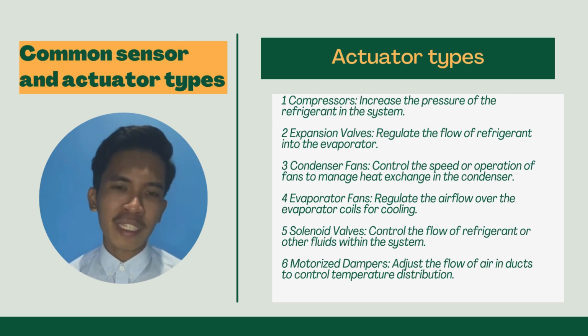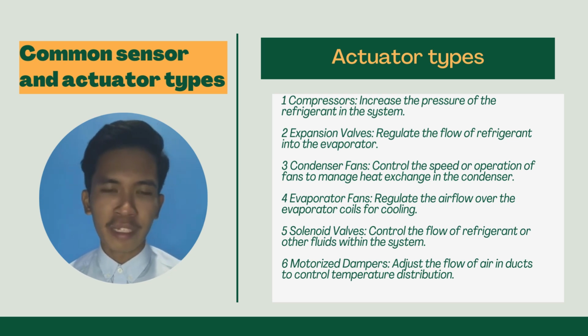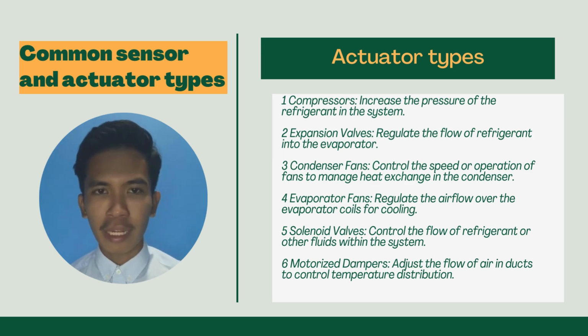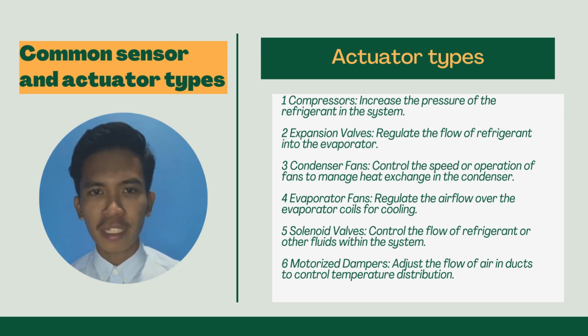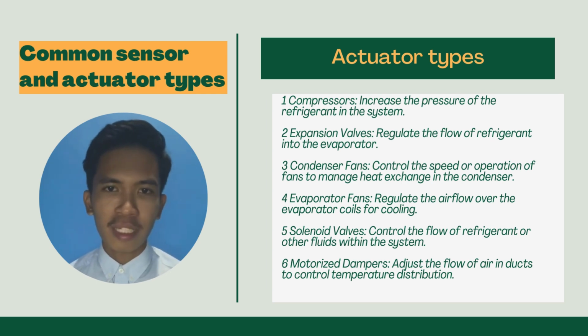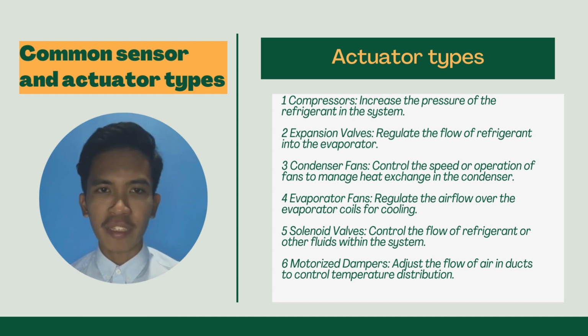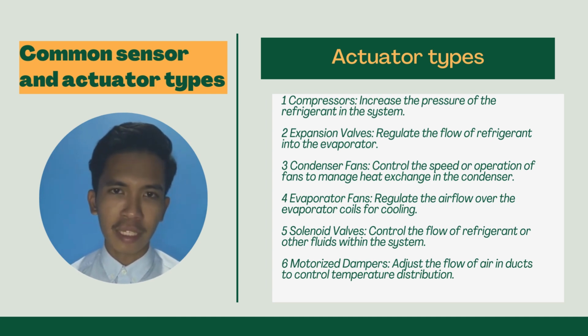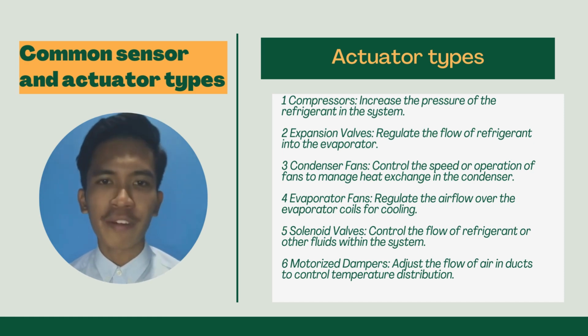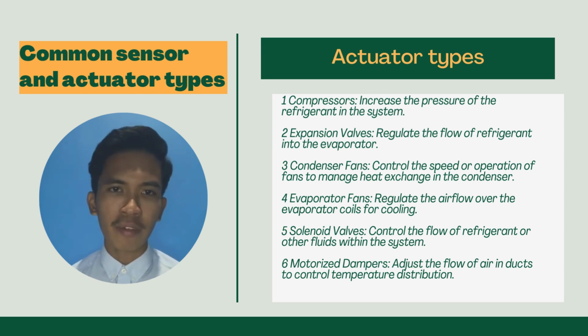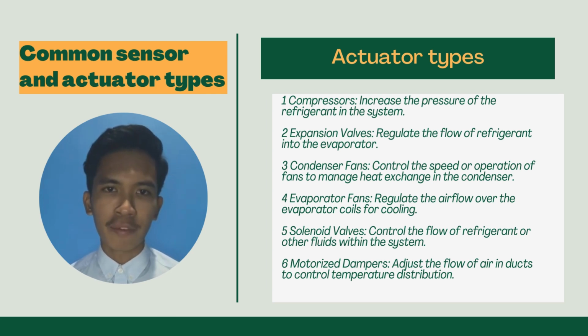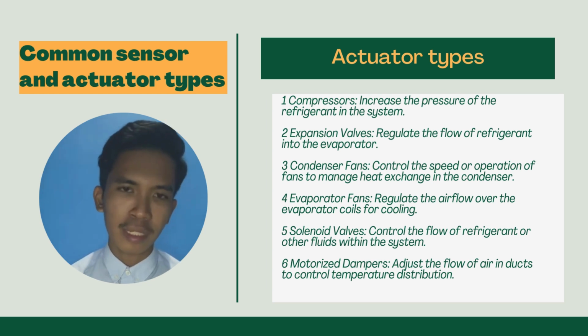Now we go to the actuator types. So the first one is compressor. Compressor increases the pressure of the refrigerant in the system. Number two is expansion valve. It regulates the flow of refrigerant into the evaporator. Number three, condenser fans. They control the speed or operation of fans to manage heat exchange in the condenser. And number four is evaporator fans. They regulate the airflow over the evaporator coil for cooling. Number five is solenoid valve. It controls the flow of refrigerant or other fluids within the system. Number six is motorized damper. It adjusts the flow of air in the duct to control temperature distribution.